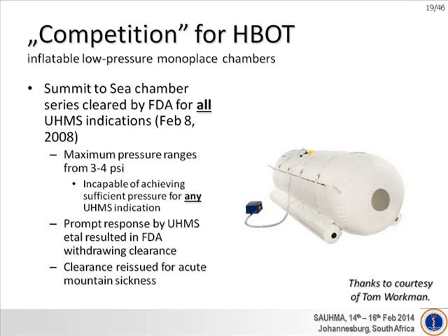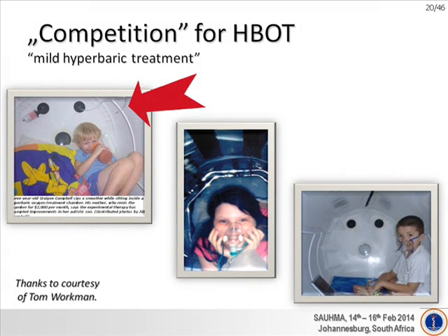And in fact, we can see that monoplace chambers or low and mild hyperbaric treatment is quite frequently used by people. And the problem is not only using those hyperbaric chambers, but also the installation of oxygen inside. Because theoretically speaking, monoplace chambers in this edition or the low hyperbaric pressure treatment modalities should not use oxygen while inside these devices. I saw pictures, however I do not have them with me, that kids are also using computers while breathing oxygen in an open circuit inside the inflatable monoplace chamber. So definitely these are hazards.